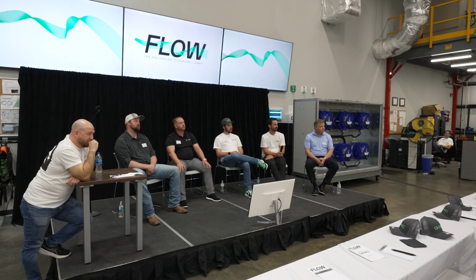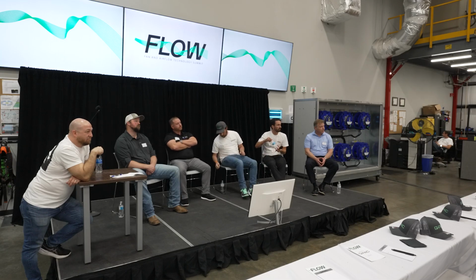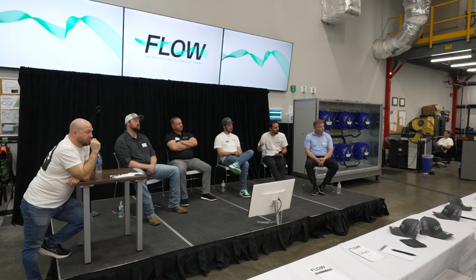I briefly talked to Matt about this on the side, but when I see an EC fan array or a multi-motor plenum fan with EC motors, the big red flag is that they sometimes introduce harmonics into the system. We've usually applied harmonic filters, either passive or active, from brands like MTE or TCI to help mitigate this, but we've run into issues with certain filters and certain EC motors in the past. I was wondering if you guys plan on doing any testing upstream of your fan controller to incorporate these types of harmonic filters, because I know a lot of critical facilities will question that.